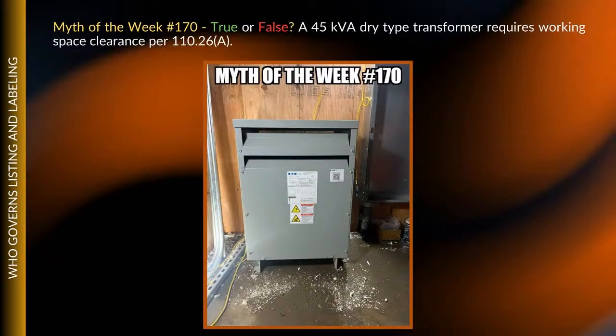Now we're talking about equipment that's going to be worked on energized. For equipment likely to require examination, adjustment, servicing, or maintenance while energized, working space must comply with A1 through A4. It's important to remember examination includes measuring voltage, so if the equipment is likely to have voltage measured there, then 110.26A applies. I think we're all going to agree it applies to panel boards, pretty much without exception. Does it apply to transformers?